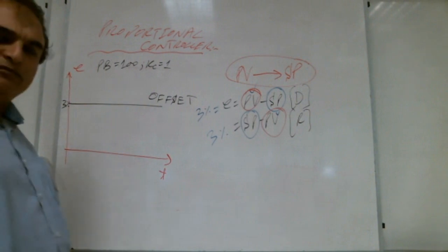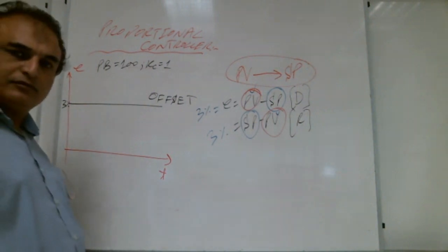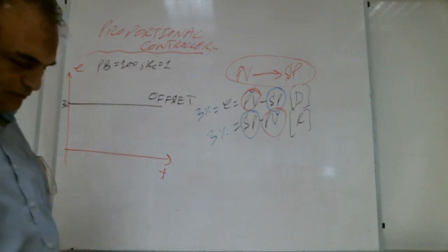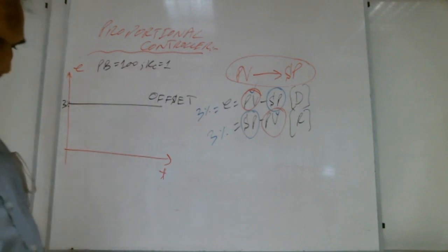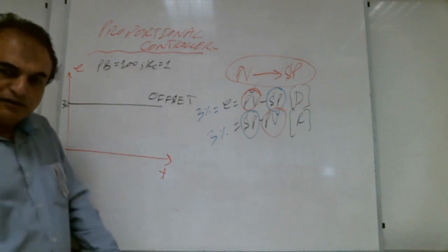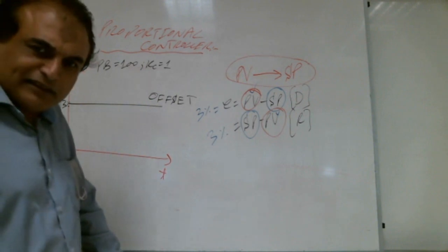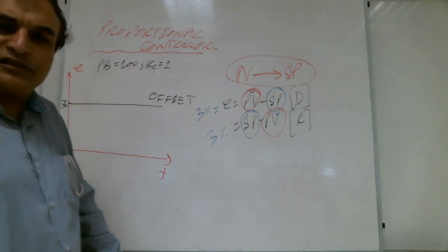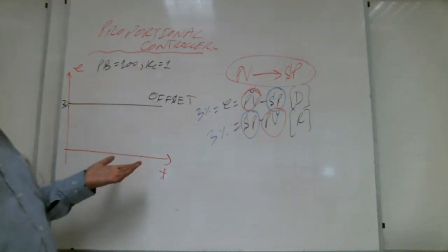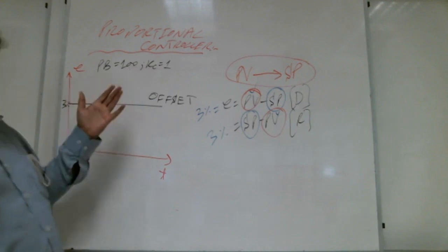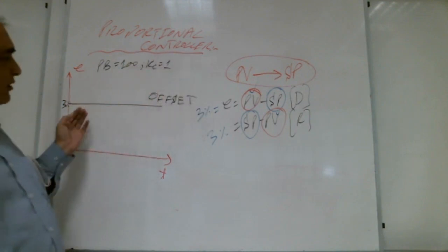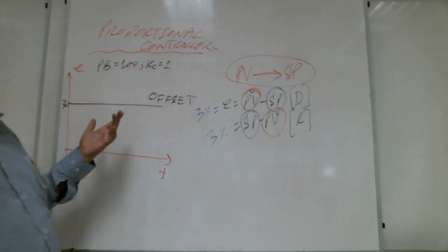How can we change it? One brother is saying integration. Integration. Is there any other solution before that? A lot of brothers are writing change the manual reset. We will change the manual reset. So again, what will happen? If we increase the manual reset, then again PV will start increasing, right? So again the error will be constant there.